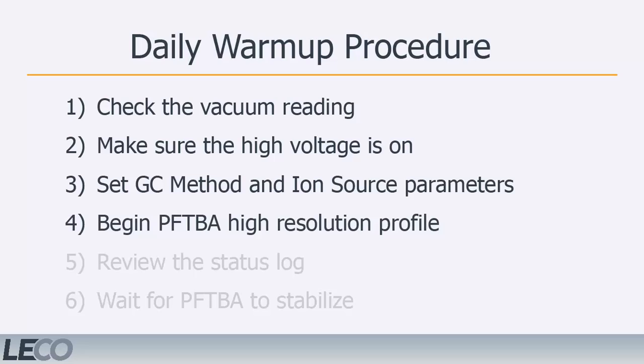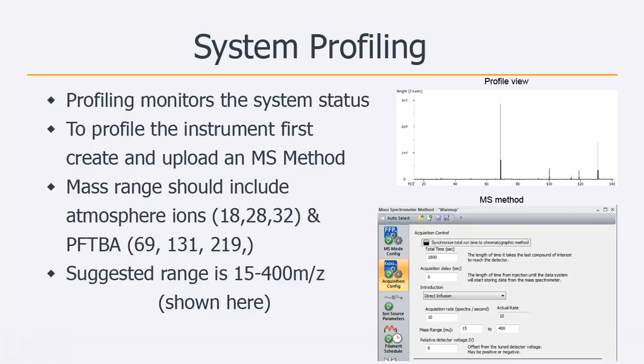Step 4. Start the PFTBA high-resolution profile. Profiling will allow the user to monitor the system status. To begin profiling the instrument, you will need to upload a high-resolution MS method that contains a mass range adequate enough to monitor both the presence of a leak and the stability of PFTBA. The recommended mass range to monitor is 15 to 400, but this may be adjusted to satisfy analytical needs.